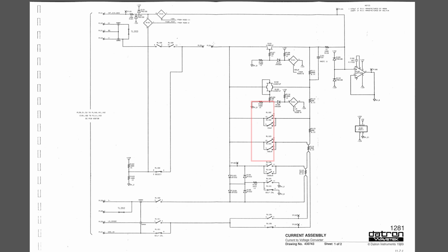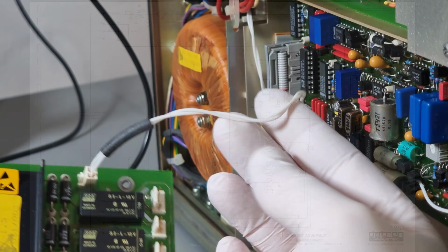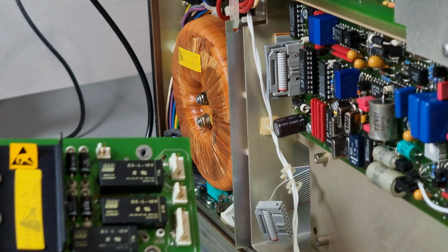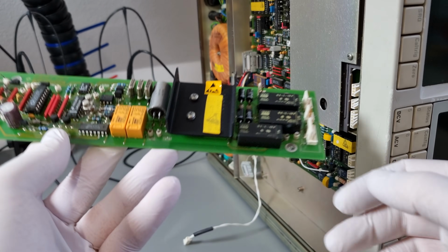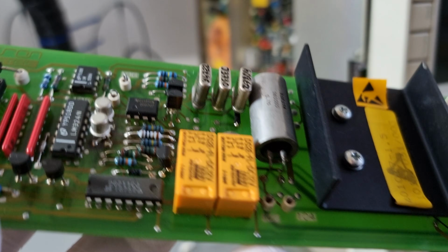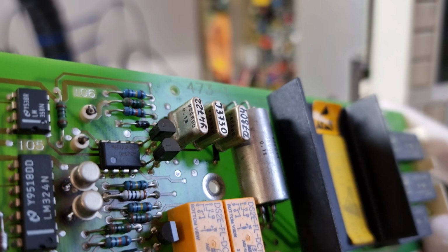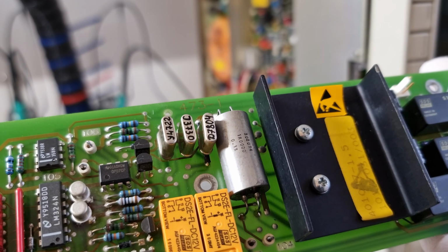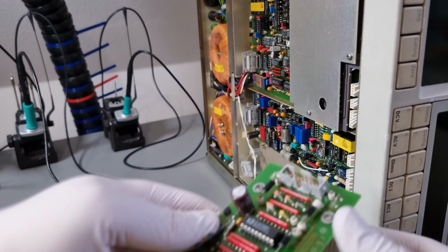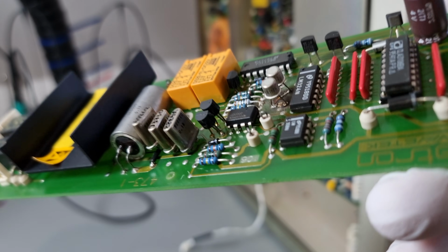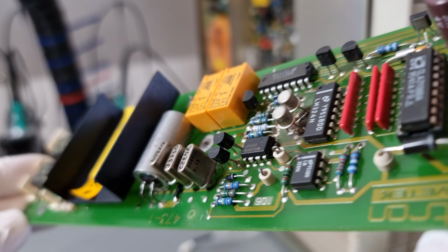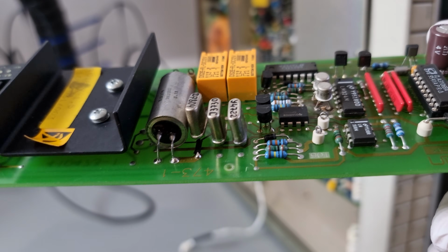There is a pretty significant channel on resistance, however, which is why JFETs can't be used to switch higher currents. The aforementioned fuse detour all the way to the rear of the instrument is connected between these 2 pins. The twistedness of the cable gives this branch what's called a small loop area, and therefore some inherent EMI resilience. The resistors with which this shunt string is built are 3 Vishay VHZ hermetic bulk metal foilers, which the manufacturer calls secondary standards in their datasheet. And then there is one axial, probably HZ series hermetic bulk metal foil resistor, which is even more fancy than the others because it's made from multiple resistor chips in parallel. Absolutely superb components, probably chosen for low long-term drift, as opposed to, say, VHP series, which is, I think, more tuned towards low tempco.